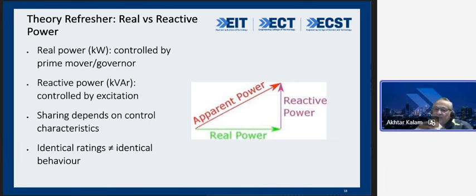And this is where the theory actually matters. I want to take you to that for a particular reason, my friends: I want you to see that real and reactive power are controlled by different mechanisms, and the confusion of the two creates a real problem. Real power is controlled by the prime mover or governor. Reactive power is controlled by excitation, and sharing depends on the control. Unfortunately, identical ratings and identical behavior are not the same.